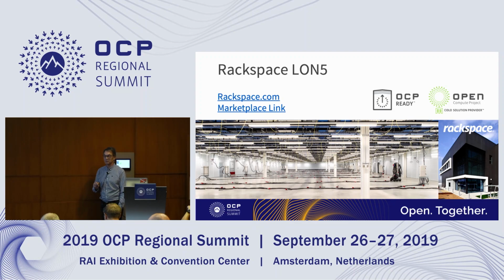We have Rackspace, as I'm sure you're aware, one of the founders of the OCP. That facility is in Crawley, south of London. It's got a white space area of 6,600 square meters and a power capacity overall of 12 megawatts. They're able to support racks up to 16 kilowatts in IT load, and also achieve 12 degrees delta T. So they're able to meet some of the optimum requirements of the OCP Ready site assessment.